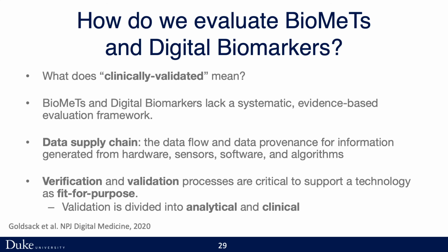And so through that, we have a 3-stage process that we've developed, starting with verification, which is almost like the bench verification, making sure that the tool works as intended. The way we think about this is if we have an accelerometer and we put it on a shake plate where the RPM are well established, we are able to replicate that in the accelerometer. And then we have 2 validation processes.